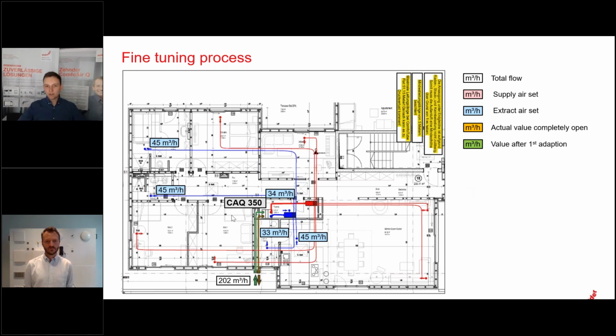At the beginning, when all valves are fully open, the volume flows will be quite similar, with slight differences due to different pressure drops in the air distribution system. The inlets which are closer to the unit have a bit more, like 43, 42 cubic meters per hour. The ones further away have a bit lower volume flows, of course, like 38 cubic meters per hour. These values are marked in orange or in yellow in that case. So now we recommend starting with the valves that are close to the unit and have the lowest set points. So we adapt these two valves first. We need 34 cubic meters per hour, but we have 43 at the moment.